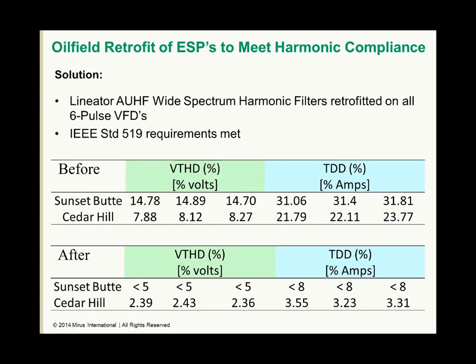So the wide spectrum filters were applied to numerous variable speed drives at the site, and with the voltage distortion before, you can see the levels at the 2 utility substations, and after we were comfortably below 5% voltage distortion and 8% current distortion, which was the requirements due to the short circuit ratio as per IEEE 519. For those interested, we have an IEEE peer-reviewed technical paper describing this application, which can be found on our website.